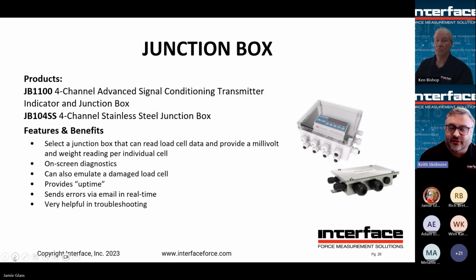And then something like a digital junction box goes a step further and actually measures each signal independently and adds them together digitally afterwards. Those are useful, say, for troubleshooting. You can actually see what each load cell is doing. So if there's a problem, isolate it more quickly than with an analog junction box. You also may be able to query it and get the individual load readings into a PLC or some remote device. Next slide.